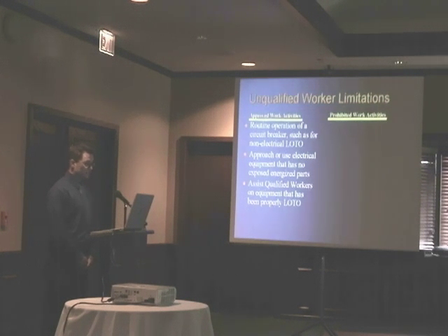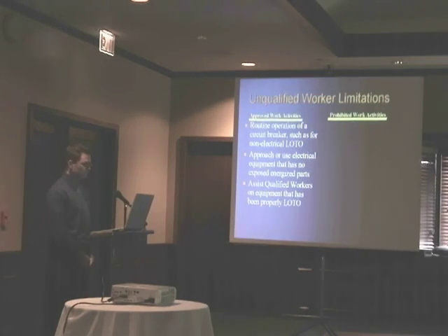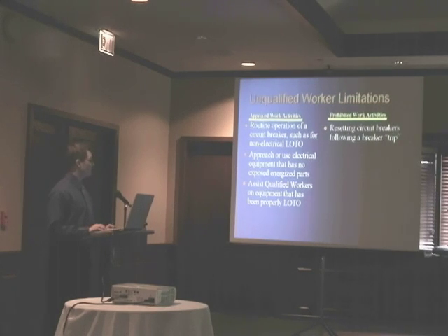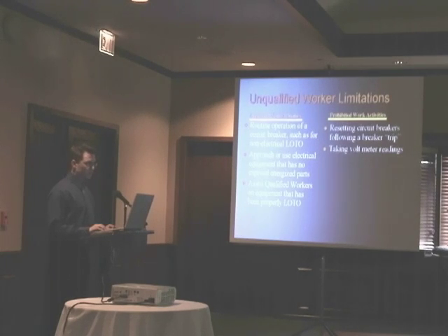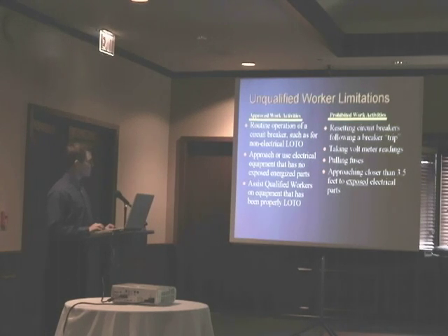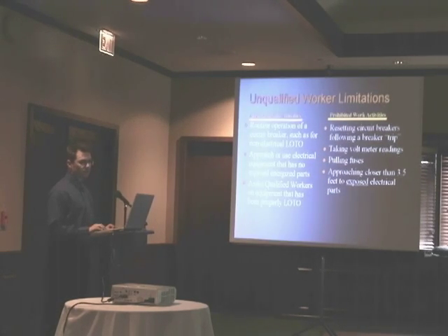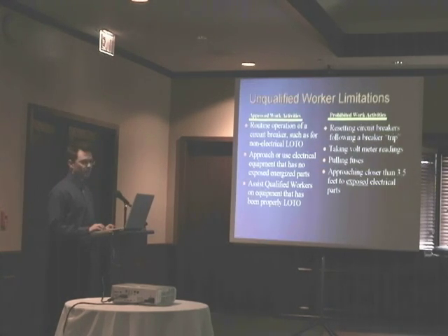Okay, approved work activities: routine operation of a circuit breaker, such as in non-electrical lockout tagout. He can approach or use electrical equipment that has no exposed energized parts. And he can assist qualified workers on equipment that has been properly locked out and tagged out. Now, prohibited work activities: he cannot reset circuit breakers following a trip, take voltmeter readings, pull fuses, or approach closer than 3.5 feet to the exposed electrical parts. This is shown by the ranges that I've gone over earlier.